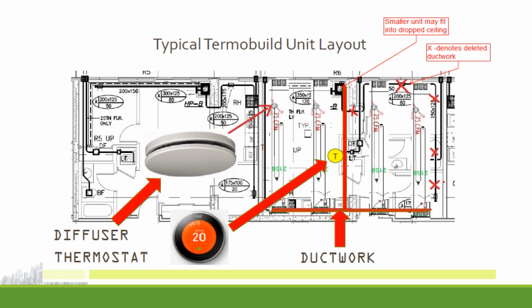The perimeter ducting mentioned on the previous graph can be eliminated, shown by the X's here. This is one of the things we do during the design process: take building systems and reduce or eliminate them because they're not needed anymore. This is the ductwork necessary for an integrated ventilation design, shown in red. So there's less ducting and less intrusion into the space, giving occupants better aesthetics and higher ceilings. You can maintain ceiling height and get rid of drop ceilings to gain space, possibly add floors, and save money when constructing the building.